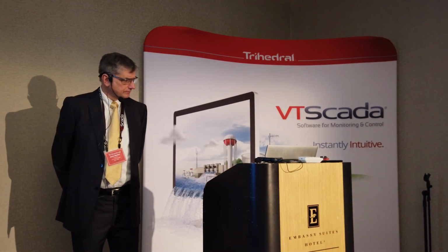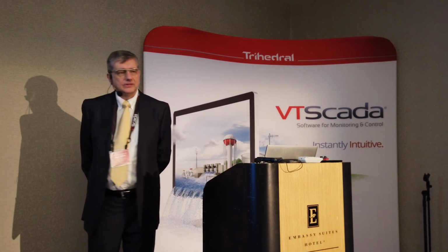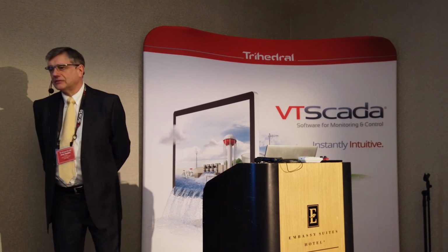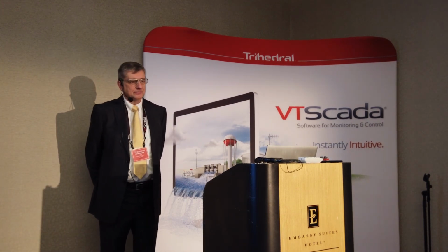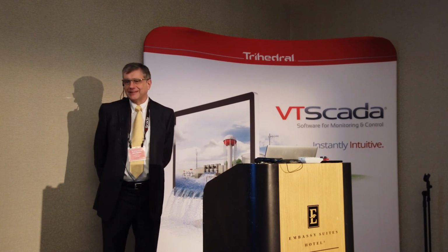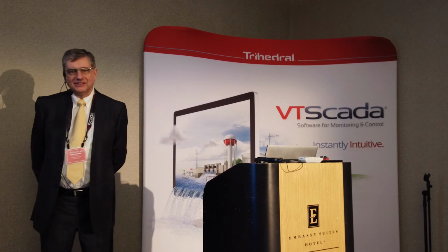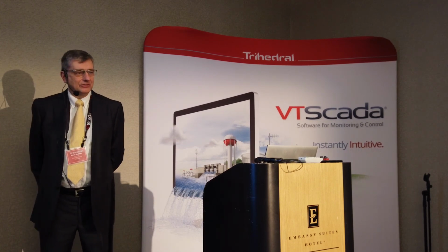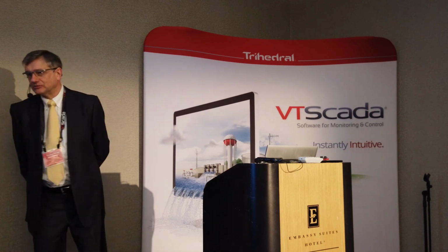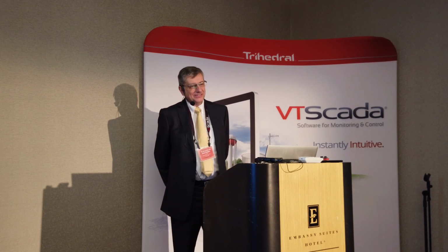So with that 1 second poll rate too, you have to ask yourself, do I really need to see that data every second? Am I okay with seeing it every 10 seconds? 10 seconds means your system can be 10 times bigger for the same computer capacity. That makes a big difference. Some data you don't need to see that often. If it's a tank level, how fast can it really move? Well, you better hope it doesn't move that fast. And if you don't see it, does it make much difference if you see it 10 seconds later or not?